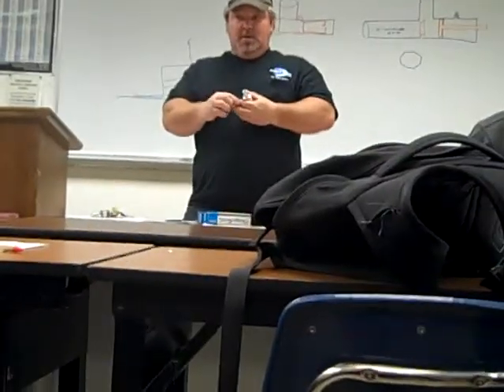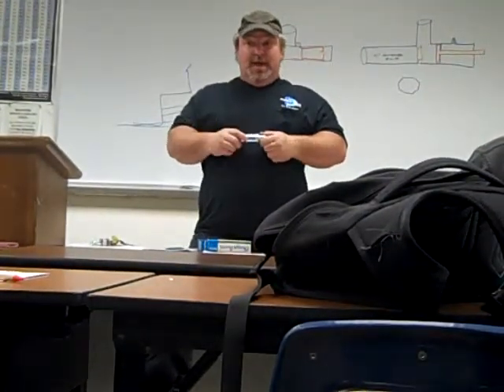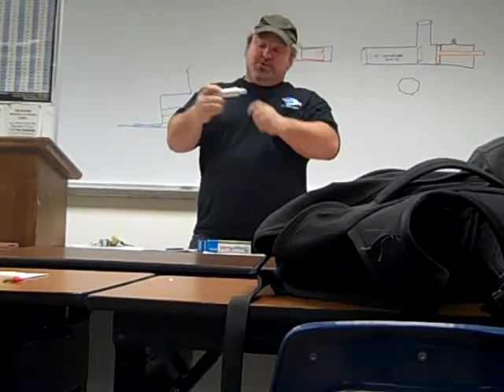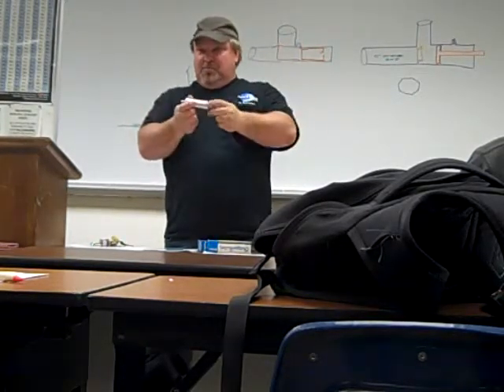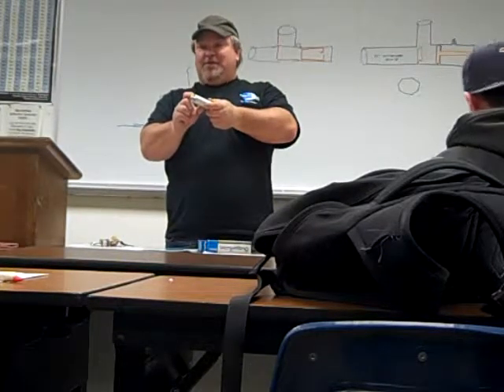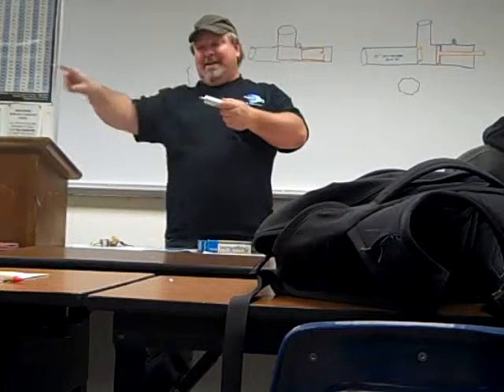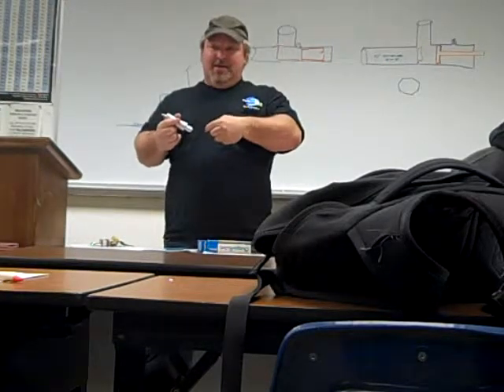Most of the time, they want you to charge it as a vapor anyway, through most systems, so you just won't slug the compressor. Not 410, you gotta charge 410 as a liquid. That's where you use one of these. You screw this onto your tank, take it out from your tank upside down, hook your refrigerant hose onto here. It comes in here as a liquid, so it comes out of the tank as a liquid, which means it's coming out under ideal mixed conditions. And inside here, it flashes to a vapor. It comes out of here as a vapor. Once it gets in the system, it doesn't matter if it's a liquid or a vapor. It's going to do what it has to do. It's just getting it out of that tank as a liquid so that it's a pure blend of what it needs to be. You can use these.